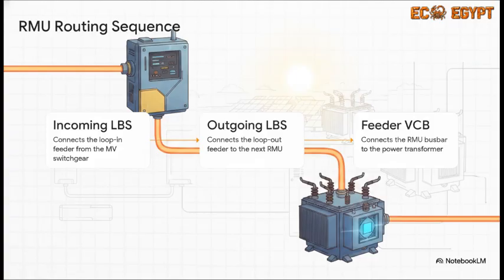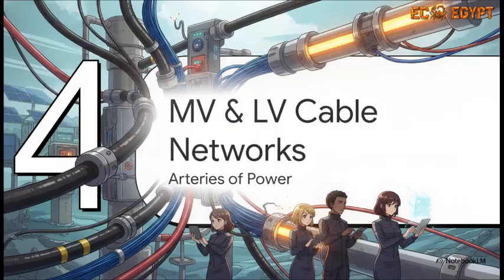It can either continue down the line to the next station in the loop through the outgoing load break switch, LBS2, or it can route downwards through a highly protective vacuum circuit breaker, or VCB, going directly into the local power transformer. It's a really elegant traffic control system. Next up, Section 4, MV and LV cable networks.